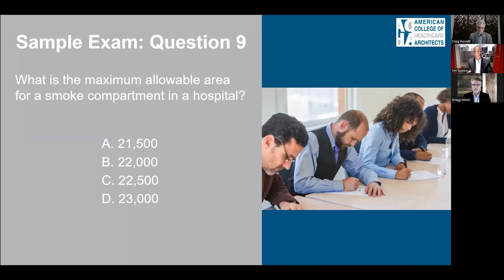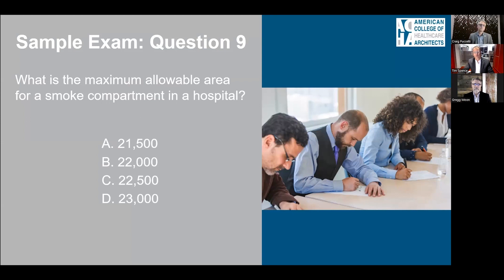Question nine: What is the maximum allowable area for a smoke compartment in a hospital? This is a pure recall question — you either know it or you don't. The answer is C: 22,500 square feet per compartment maximum.